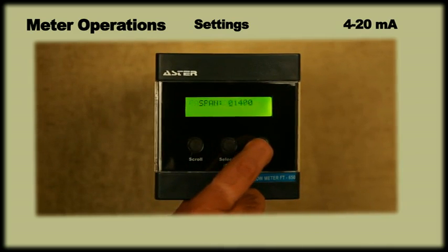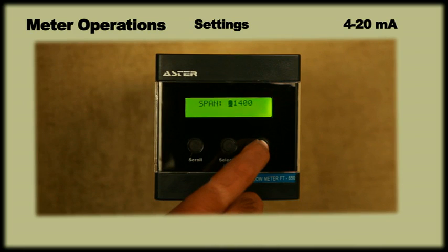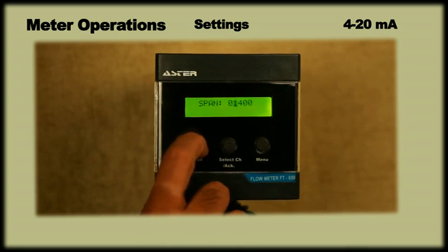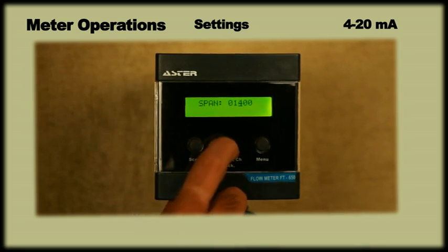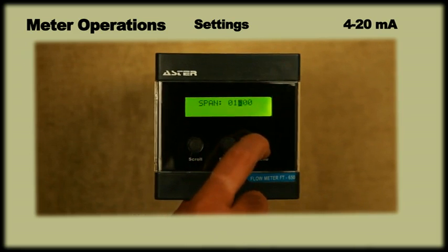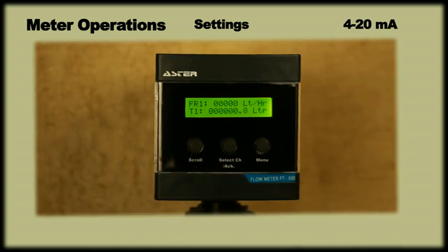Keep pressing menu until it reaches span. Press menu again. Display will show previously set span value. One can change the value using scroll and select ch key. Having changed the span value, press menu to end and save the setting.